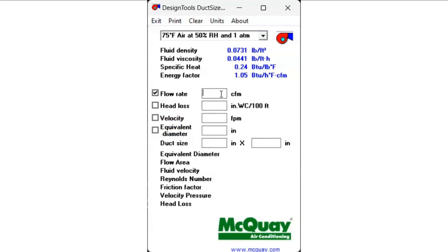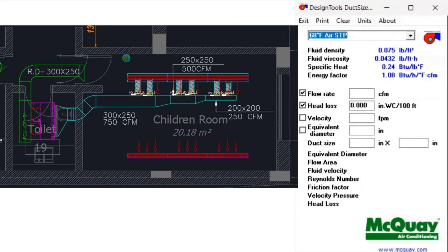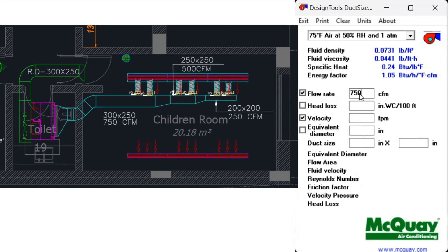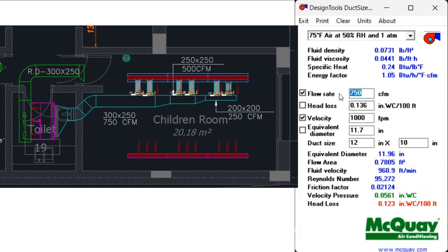Set the air properties to 75 degrees and units to IPS. You can also set units to metric based on your requirement. I am putting input values of airflow rate 750 CFM and velocity 1000 FPM — the duct size comes out to 12 inch width and 10 inch height. The friction value for this duct size is 0.123 inch of water column per 100 feet.